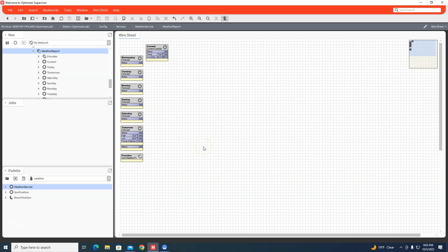You can have a setpoint - say 80 percent. If there's an 80 percent chance it's going to rain tomorrow, disable the sprinkler system for tomorrow. I can't tell you how many times I've seen it raining outside and the sprinklers are going. That's water conservation. If you have a 100 percent chance of rain tomorrow, there's no need to run the sprinklers today. You can put a 48-hour reset on the sprinkler system, and if it doesn't rain, you just run it the day after.